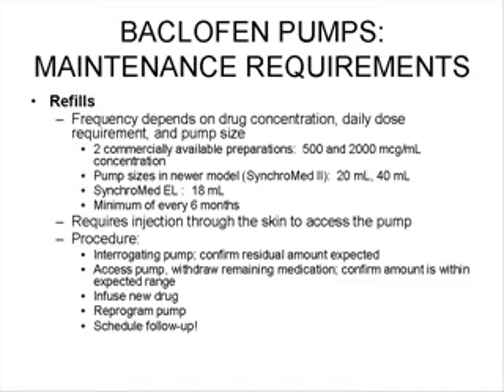At minimum, because of FDA regulations for how long the drug can remain in the system, you have to be refilled every 6 months, even though you're not empty. So every 6 months at minimum is the amount of the refill. And people will vary between every 1 to 6 months depending on the dose and concentration. So the refill does require an injection through the skin to access the pump.